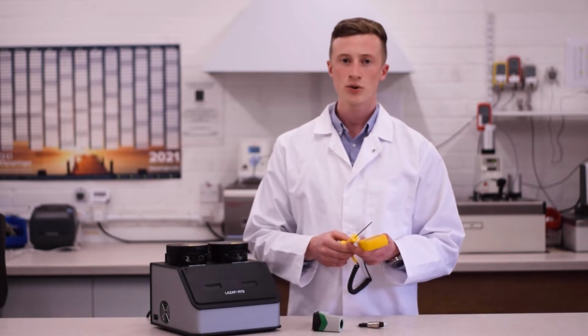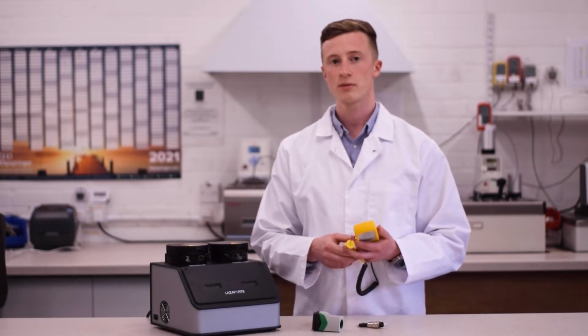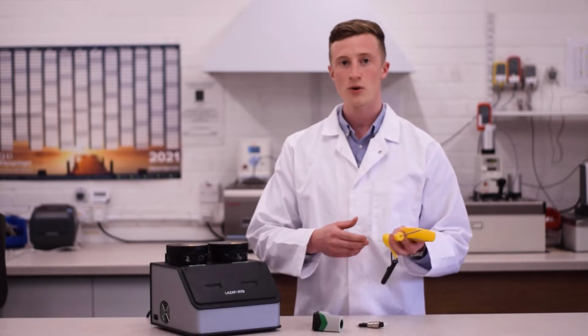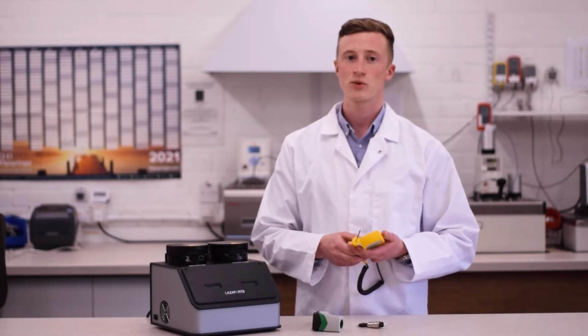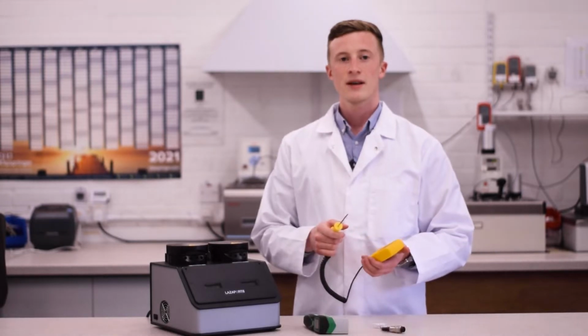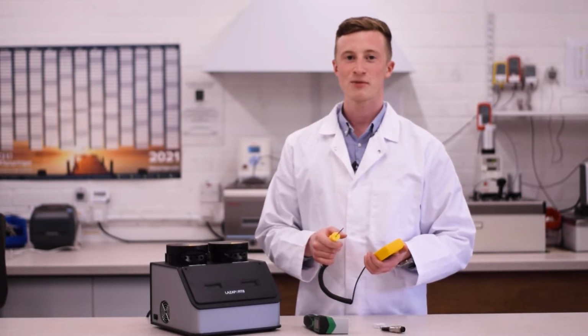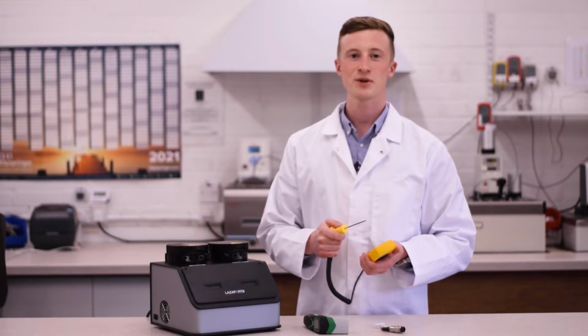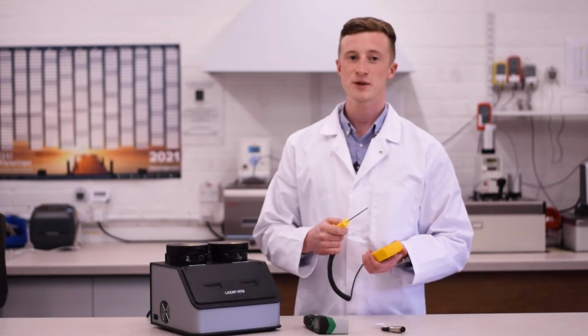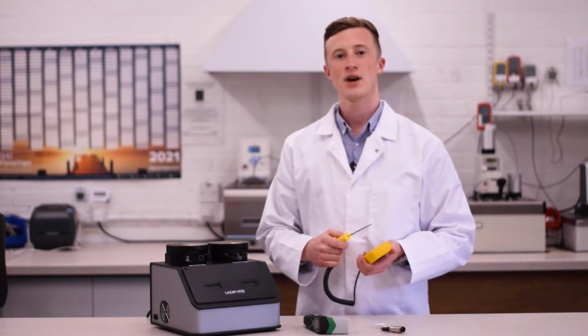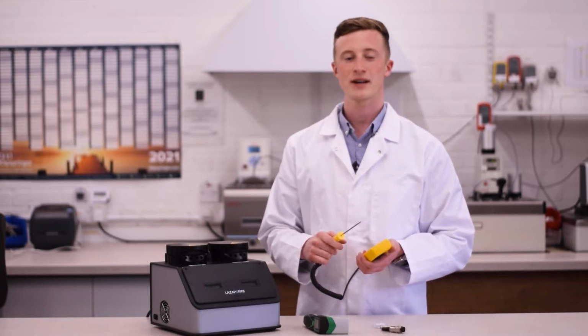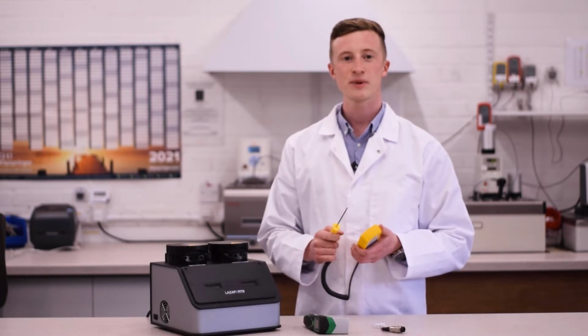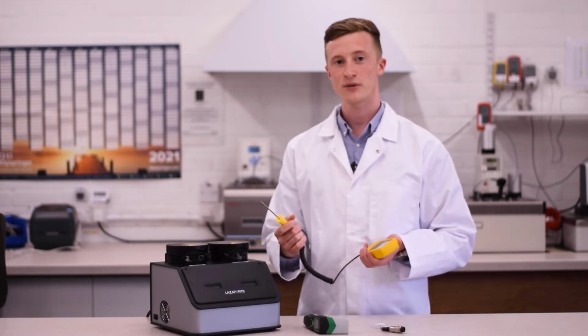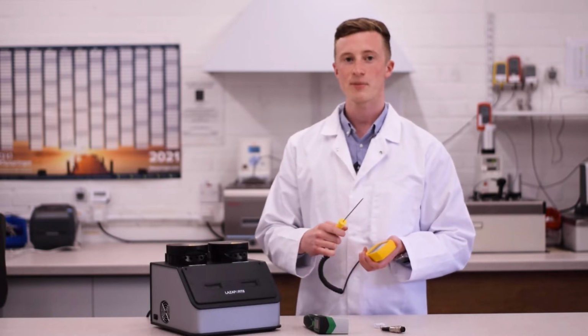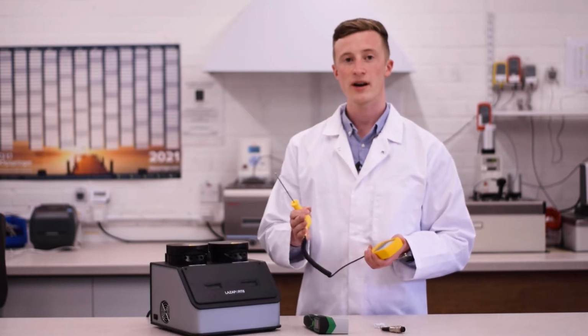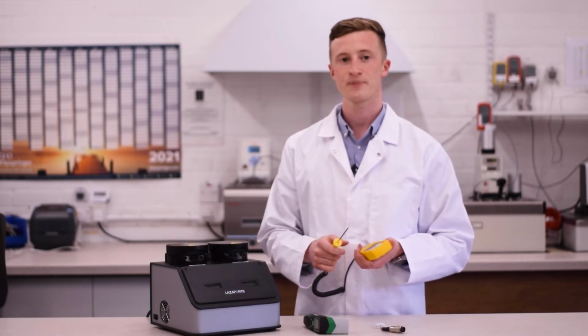Second, check at 2 temperatures to check the range of the thermometer. This could be at 0 and 100 or whatever is applicable to your testing range. The exceptional quality of Klipspringer thermometers means that when your verification procedure confirms the thermometer is within spec at 2 temperature points, we can guarantee it is within spec across the whole range. This means checking at 0 and 100, for example, is sufficient for any applications where you may need to measure higher than 100 degrees Celsius.